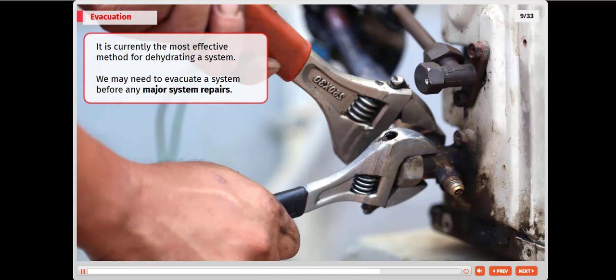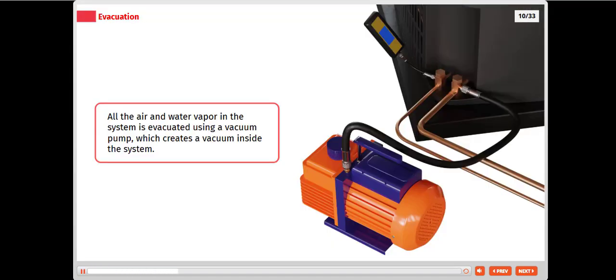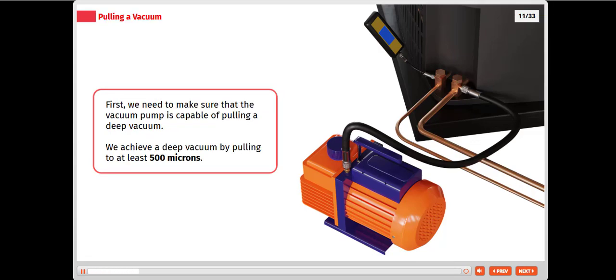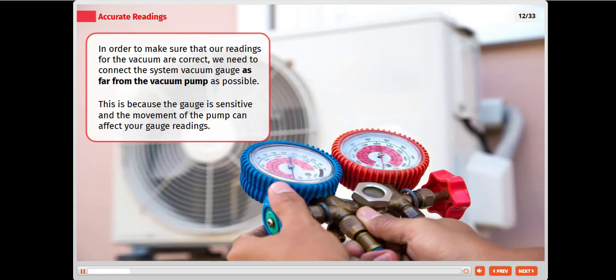All the air and water vapor in the system is evacuated using a vacuum pump, which creates a vacuum inside the system. First, we need to make sure that the vacuum pump is capable of pulling a deep vacuum. We achieve a deep vacuum by pulling to at least 500 microns. In order to make sure that our readings for the vacuum are correct, we need to connect the system vacuum gauge as far from the vacuum pump as possible. This is because the gauge is sensitive and the movement of the pump can affect your gauge readings.